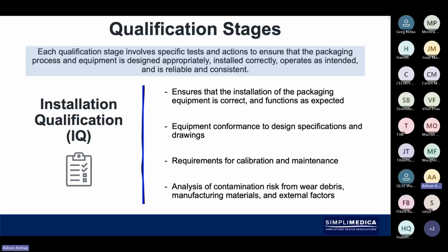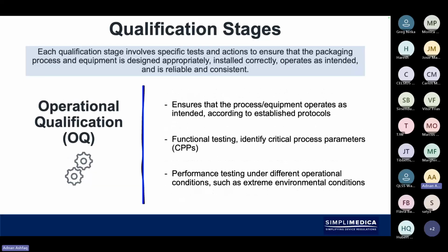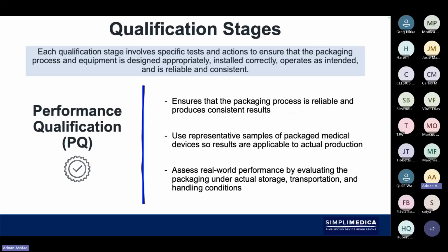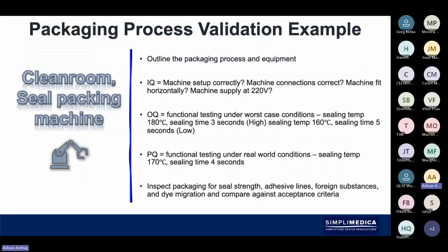I do recommend you have a look at that video, which is on the SimpliMedica YouTube channel, and you can see some of the requirements that are generally required for DQ, IQ, OQ, and PQ. Making sure that the protocols are there, making sure that you've tested the extremities, and making sure that when you get to PQ that you are documenting everything in as close to the real environment as possible, and documenting everything as such.